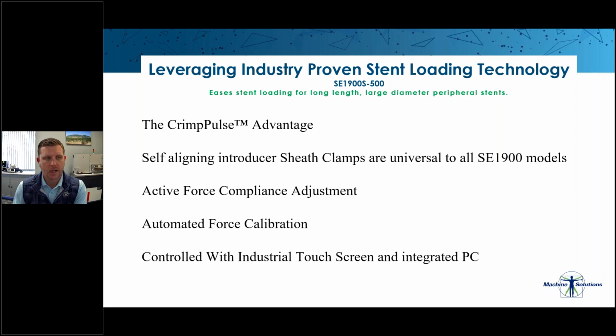So to start off, we're going to talk about the crimp pulse advantage. Crimp pulse is a patented technology that is the greatest aid when you're loading nitinol stents. The crimp pulse technology reduces the radial compression forces by vibrating the crimp head segments, which allows the stent to travel through the head under compression with ease. Radial compression forces are generated when a stent is compressed inside the crimp head, and a nitinol stent is constantly trying to return to its expanded form. So high radial forces can cause the stent to lodge itself between the Ertalyte material of the segments in the compression head. And for larger stents, the forces can tend to rise above 40 pounds of compression force. And that is why the crimp pulse vibration feature is such an advantage in our machine.